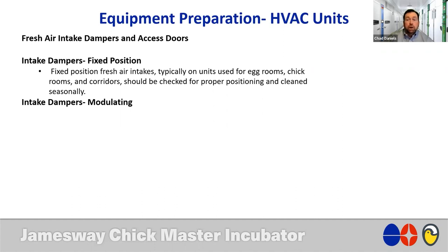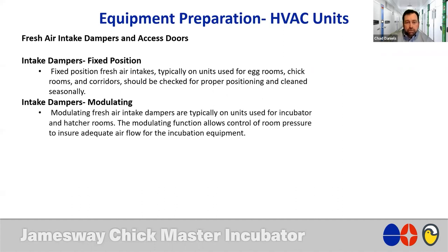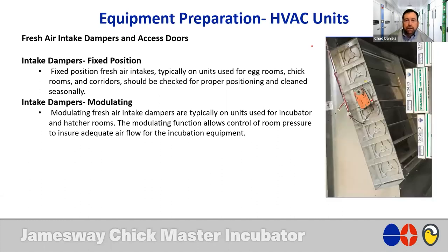Intake dampers that are modulating. Now, they modulate specifically because it is trying to control room pressure. You know, you have a pressure sensor in the room. It references to atmosphere generally, and then the damper modulates more open to bring in a higher volume of fresh air in order to meet the desired room pressure setting.